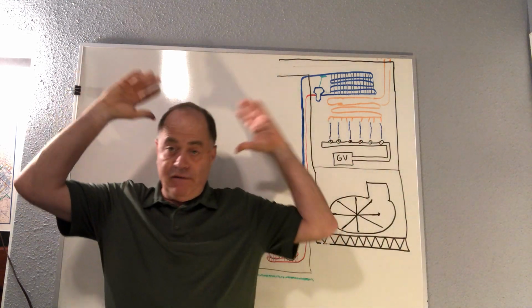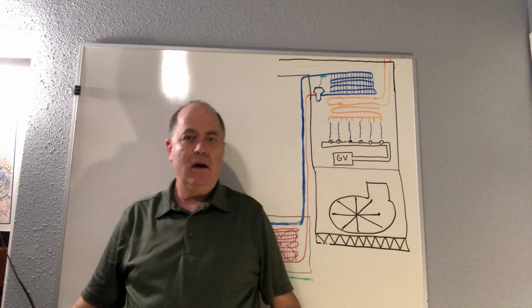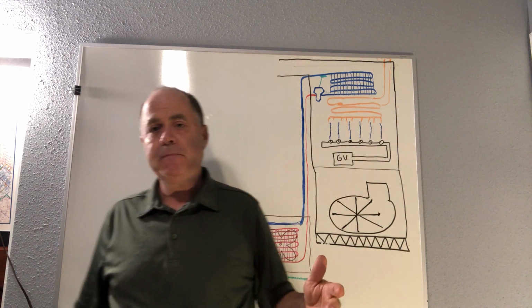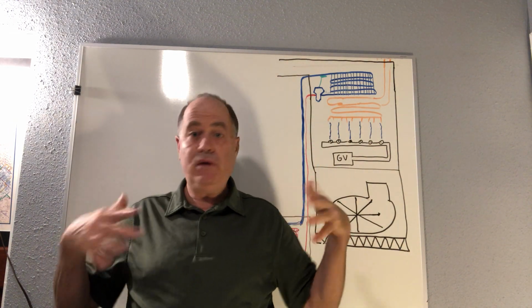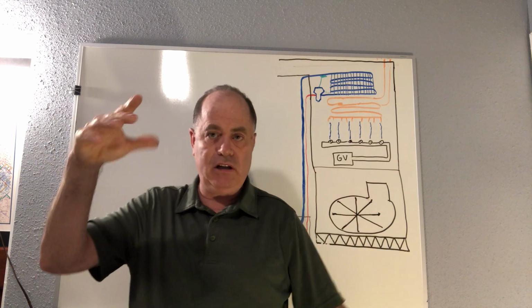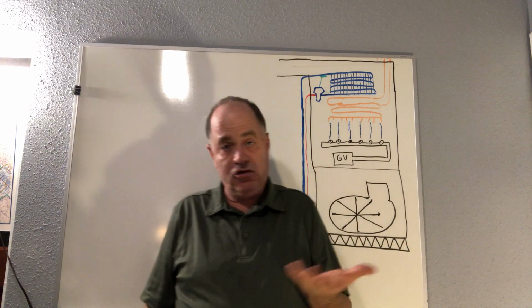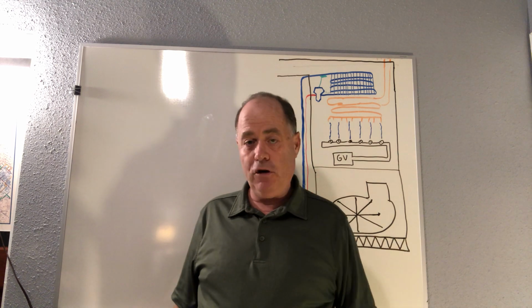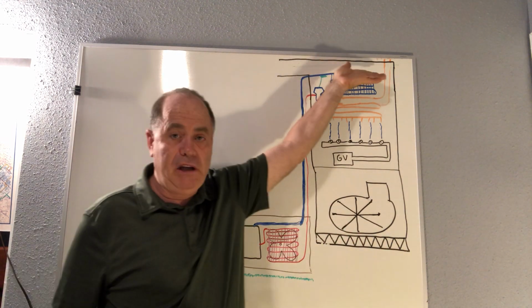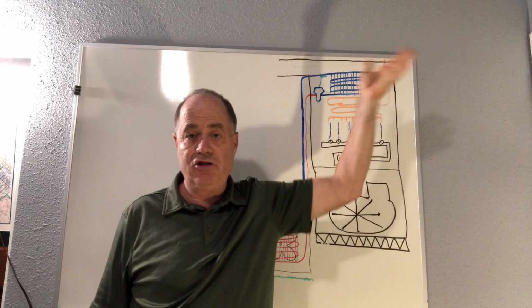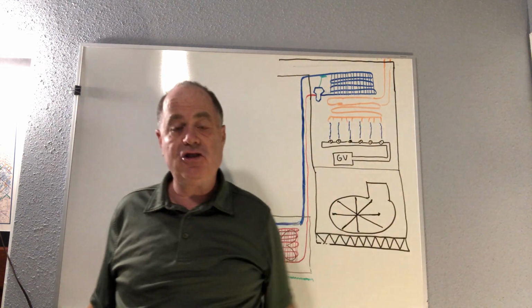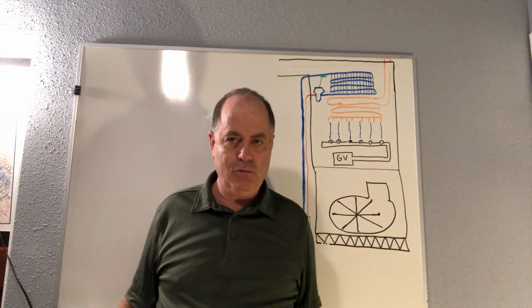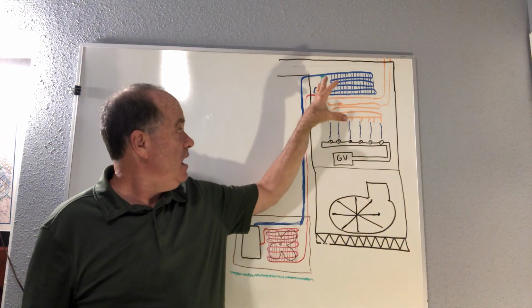Heating, you want a very slow, soft air speed. Generally, systems run their fans at low speed for heating, so you get this warm, gentle heat on you, and you don't have draftiness. You don't have a fan blowing air on you, which can make you feel cold, right? So heating is gentle, and then with cooling, we want fans, we want more air circulation, right? So there's been a history. The history of air conditioning is heating first, and then a lot of people would just jam in a cooling coil somewhere, which I've seen even in modern jobs. Old heating systems just jam in a chilled water coil, or 500 of them, which I've experienced in a school.